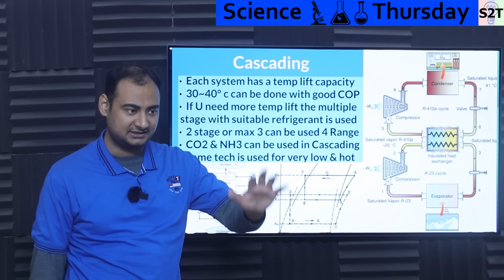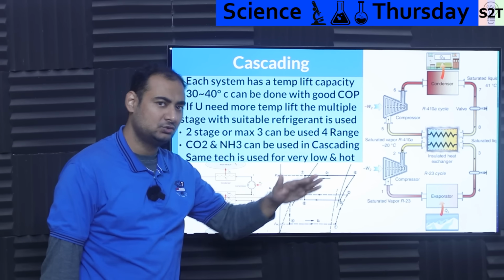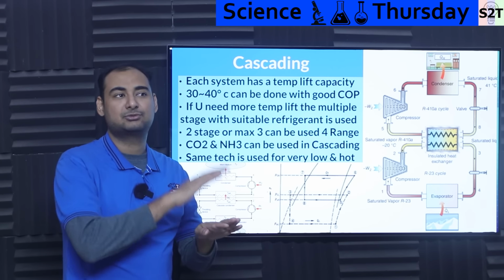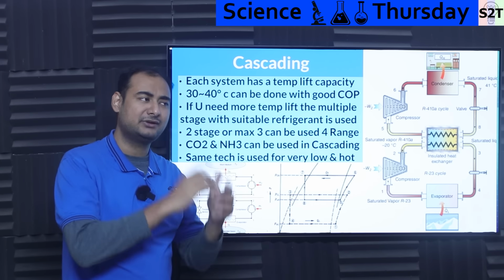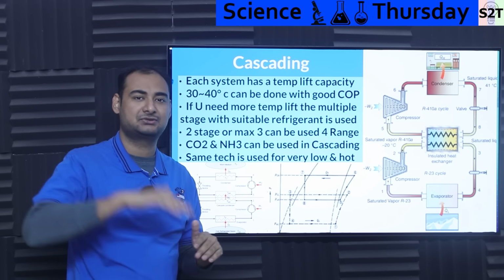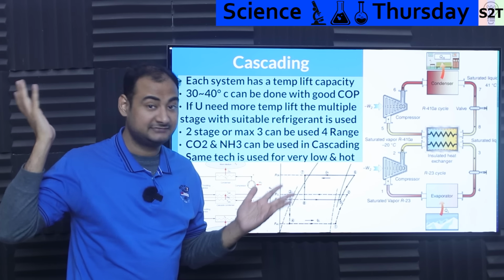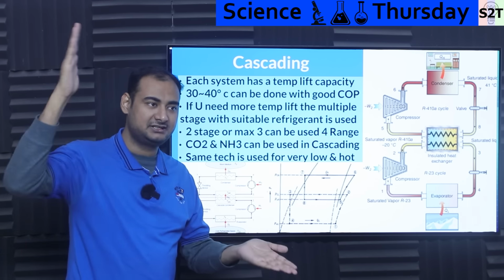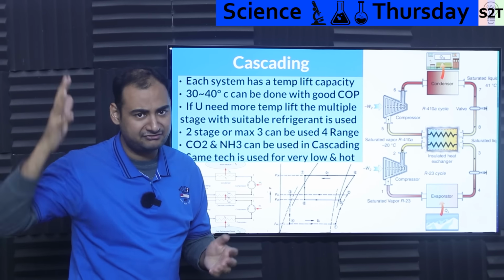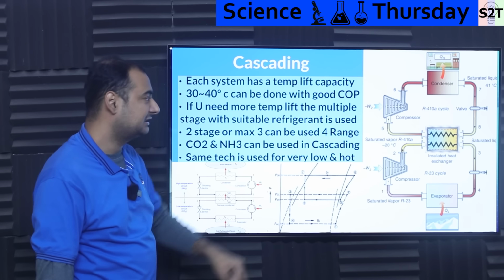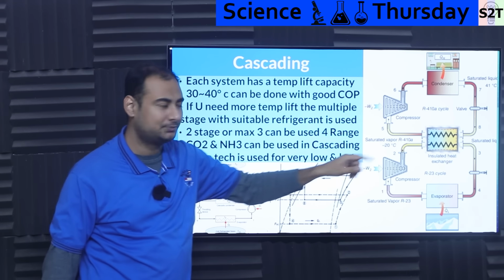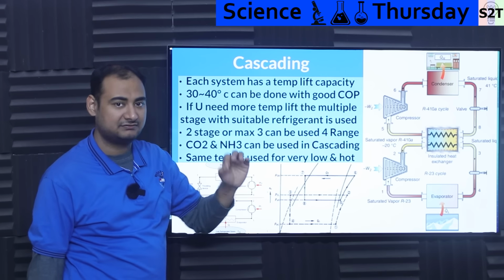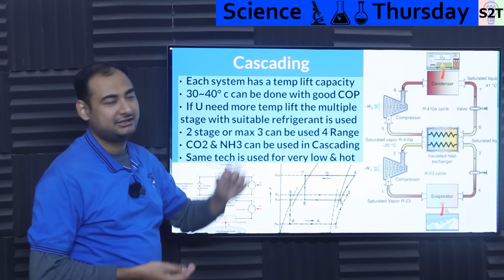So you get one cycle that goes from minus 20 degrees Celsius to 20 degrees Celsius. Then you can put CO2 — CO2 could be like, hey, 20 degrees, I can easily lift this to 20 to 70 degrees Celsius. That can be done, and the delta becomes a bit different since it's a different refrigerant. Basically, you create 2 loops, fine-tune each for their lift, and tada, you get very good COP.